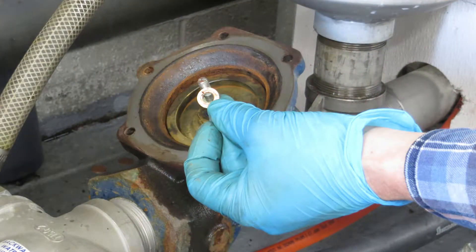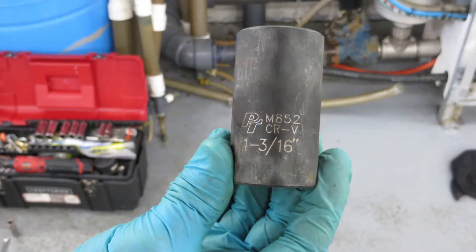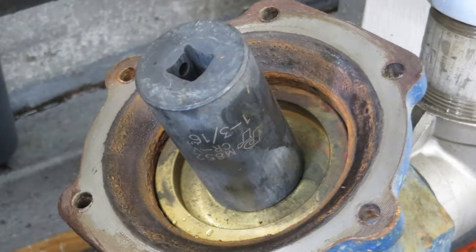There will be another copper washer that needs to be removed. The rebuild kit will have a new one so we can recycle the old one in the metals bin. We'll be looking at the nut plate with the stainless steel threaded rod in the middle. You want to press the shaft down so that we can put the one and three-sixteenths deep socket over the top. Make sure the socket is pressed all the way down onto the bronze nut because if it's not you can round off the nut when you're trying to take it off.